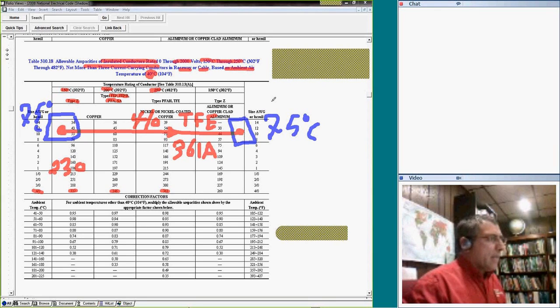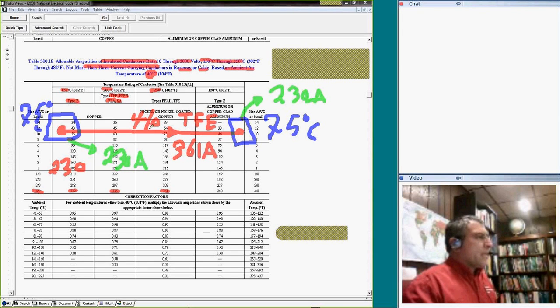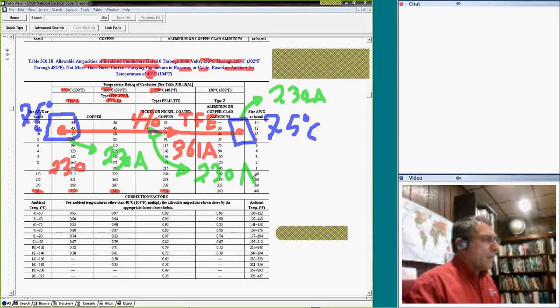But wait a minute. If you look at the lugs themselves, guys, both lugs are not rated for 250. These lugs are rated for 230 amps. So how much current can this conductor carry? It's based on the weakest link, which is 230 amps. I can't carry more than 230 amps. The question becomes, my friend Joe, why do I have these conductors? Who cares about them? You get the benefit with derating.